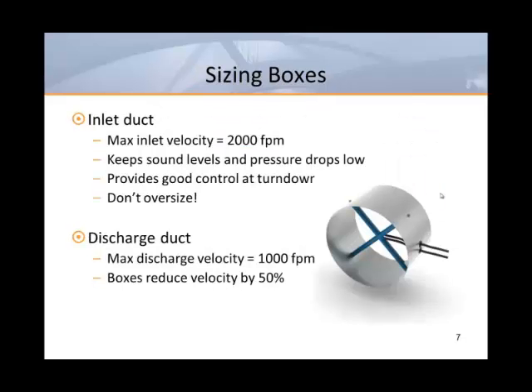So let's look at the basics of sizing boxes. My rule of thumb for sizing inlet ducts, especially for VAV applications, is to select for a maximum inlet velocity as close to 2,000 feet per minute as possible. If I don't exceed 2,000 feet per minute, I shouldn't self-generate noise in the supply ductwork, and 2,000 feet per minute will keep my pressure drops low.